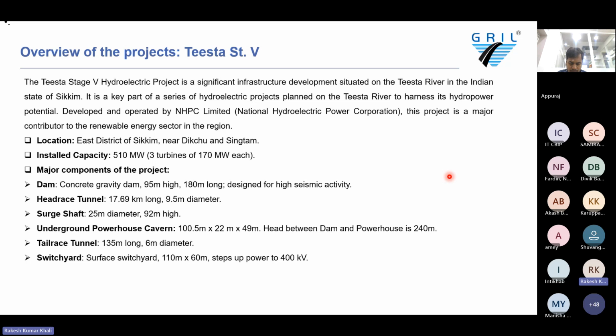Installed capacity is 510 megawatt, with three turbines of 170 megawatt already commissioned. Major components of the project: dam, a concrete gravity dam 95-meter high, 180-meter long, designed for high seismic activity. Headrace tunnel 17.69 kilometer, 9.5-meter diameter finished, excavated diameter 10.5 meter, so we used heading and benching for this.